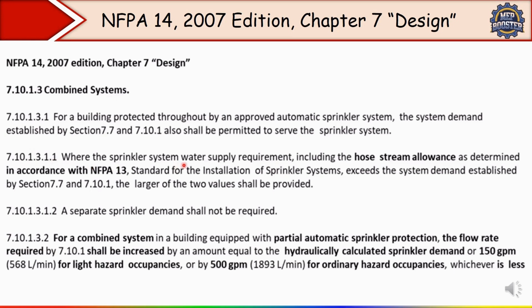You can see where the sprinkler system water supply requirement, including the hose stream allowance as determined in accordance with the NFPA 13 standard for the installation of a sprinkler system, exceeds the system demand. So here we need to calculate. First we need to do the hydraulic calculation for both. Okay, that I will explain to you. So whichever is greater, that we have to consider. It means what? This means that if the hose stream allowance water needed for fire hoses is greater than the sprinkler demand, then the higher value must be used in the design. Okay, remember this. This is the exact meaning of this point.